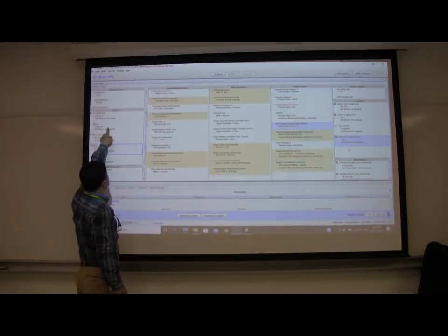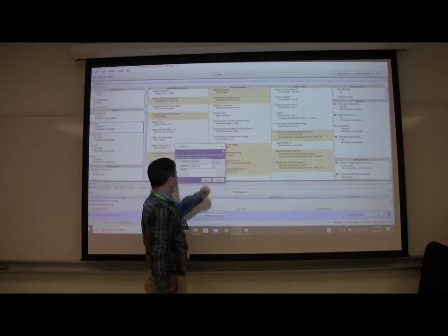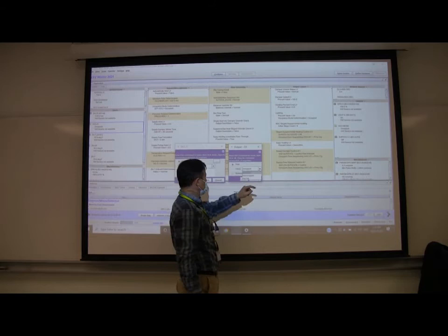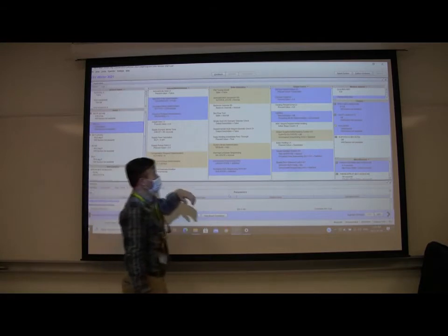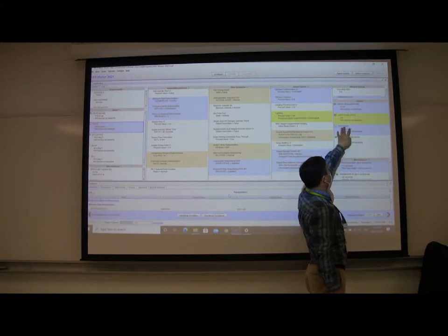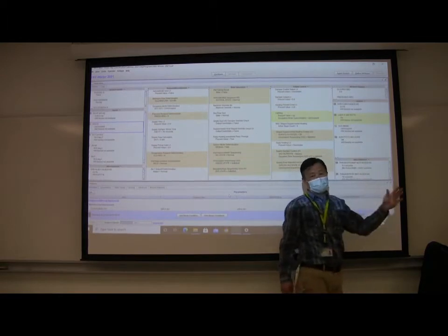Now we take this one, set this one, command, and then we set it back to unoccupied. Set unoccupied. Okay. And send. Here it's unoccupied. It should be, the lighting should be off. But now it's still on, but a little bit time delayed.